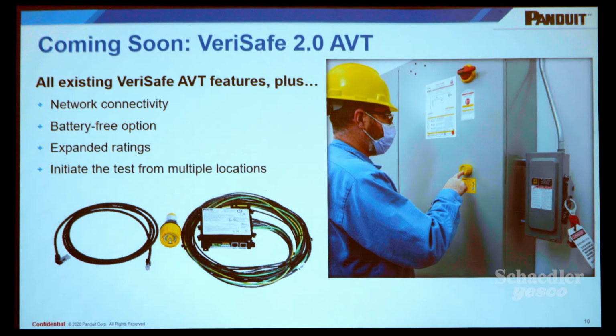Another feature that we've built into the latest version is that the indicator modules, when you disconnect the panel from power, you still need some way of powering this device to do the test. So the indicator module has a little AA lithium-ion battery in there. It's accessible from the front, but some people don't like having servicing batteries on the plant floor. So we came up with a battery-free option. That indicator module is powered up through power over Ethernet or through control voltage, either way. So you've got 3 ways of powering this up, either through a single AA battery, PoE, or a control voltage. So that version, which I have over at the booth, is coming out in July as well.